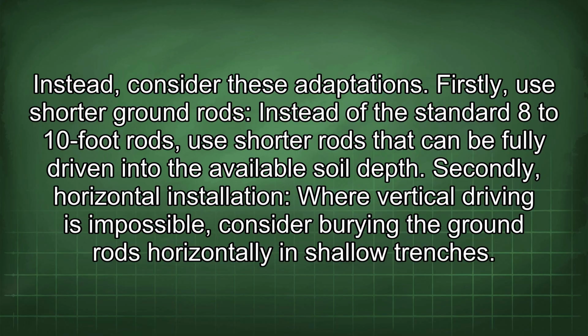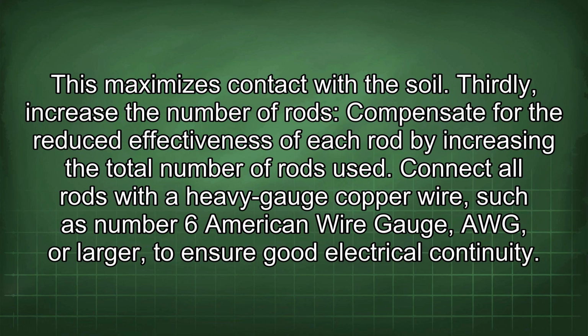Where vertical driving is impossible, consider burying the ground rods horizontally in shallow trenches. This maximizes contact with the soil. Thirdly, increase the number of rods. Compensate for the reduced effectiveness of each rod by increasing the total number of rods used. Connect all rods with a heavy gauge copper wire, such as number 6 American wire gauge, AWG, or larger, to ensure good electrical continuity.